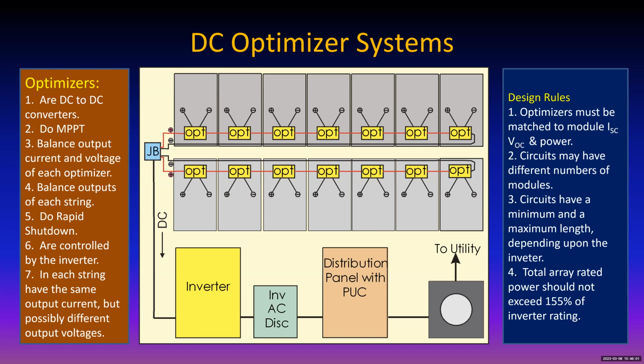And optimizers, see, in a microinverter system, you can go down to 1 module as a string, but in an optimizer system, there is a minimum number of modules and it's limited by the maximum DC output voltage of the optimizer. If the optimizer is limited to 60 volts out, and if the system's going to operate as high as 400 volts, then you got to have enough times 60. And 5 times 60 is 300. It looks like you're going to need 7 optimizers in order to get up to 400 volts. So minimum string length here is 7. In order to get your 400 volts, you need to make the inverter happy.